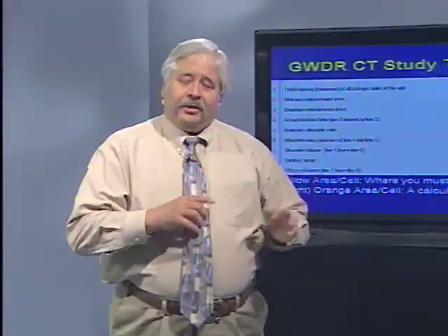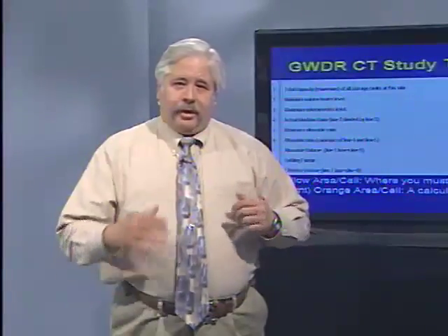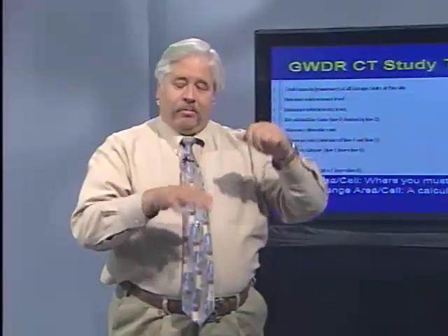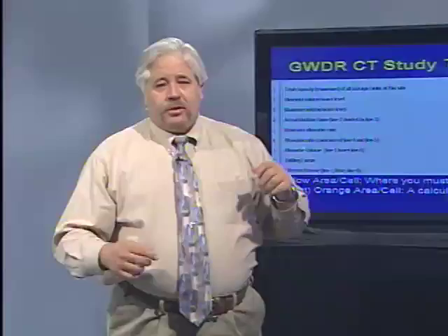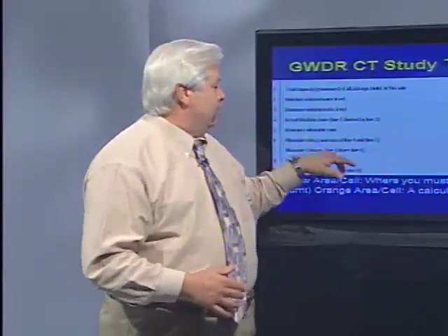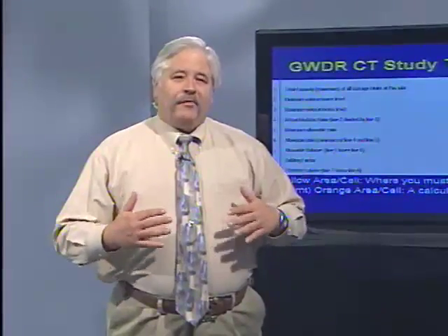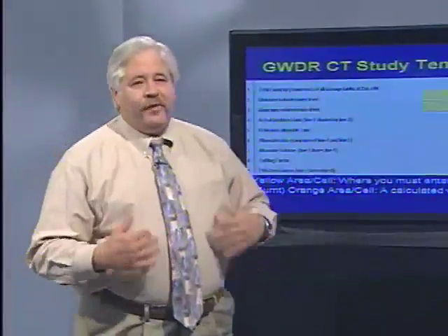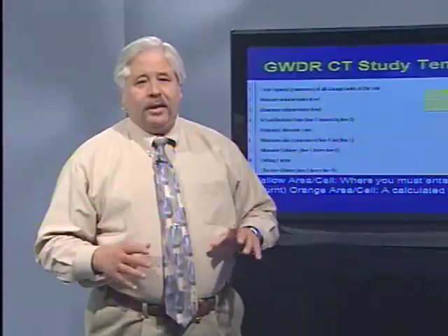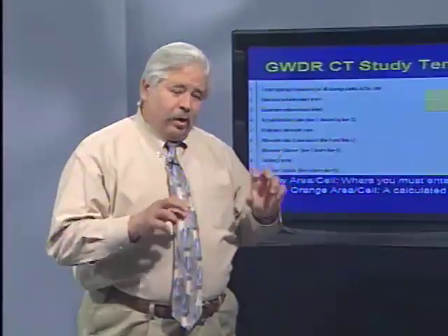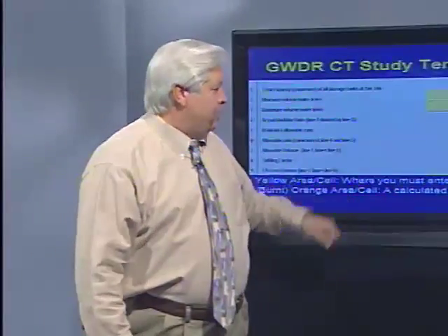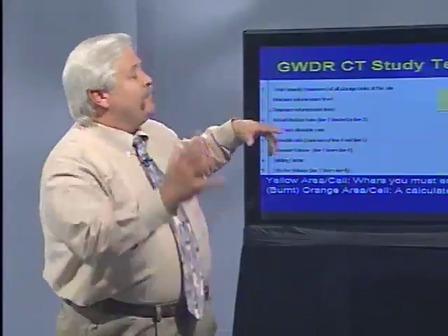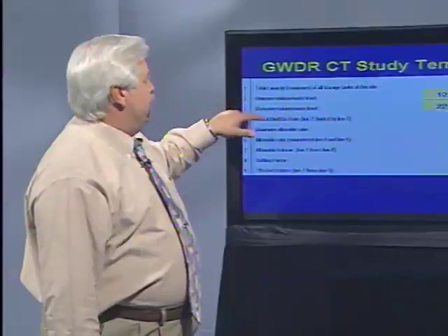However, that detention time doesn't account for any short-circuiting that occurs within the storage tank as the water enters in a jet form and leaves as a suction. So in order to compensate for that, we have to include a baffling factor. The baffling factor times the allowable volume gives you the effective volume of that tank, okay? For CT credit, not for real world supplying water to people, but for CT credit. The bottom half of the slide shows you how. Let's go to the next slide and give you an example.